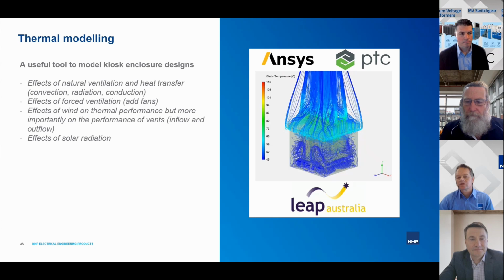And how do we do that if we're just building designs and prototyping? We can build something up, make assumptions, test it, but how do we make refinements? The key thing about the software is that you can make small tweaks, and you can actually do cross sections and see the eddies and see the effects of how the flow is working. And you can see on this diagram here, it's actually drawing lines to show the airflow. So we know we have lines that are running largely parallel to one another. We've got good laminar flow. Not always going to get it. We've got a couple of slides where we go into a bit more detail on each of these through the design and modeling path that you've followed.